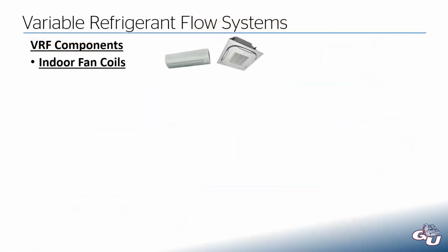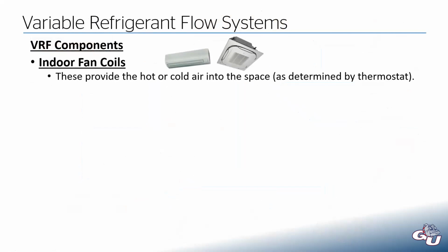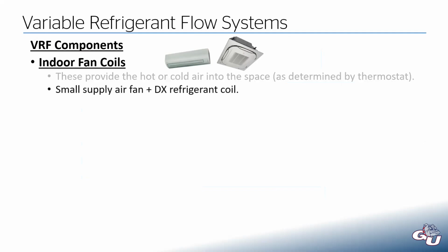So the indoor fan coils, these are the things that are going to give us our hot or our cold air into the space as determined by each individual thermostat connected into each one of those units. And all that is really in there is just a really small supply air fan and a DX refrigerant coil. And that's it. These fan coils usually recirculate air within the space. Normally they are not connected to an outside air connection point like a traditional air handling unit. So normally we have to provide ventilation air separately, and we'll get more into that down the road when we talk about heat recovery outside air systems.